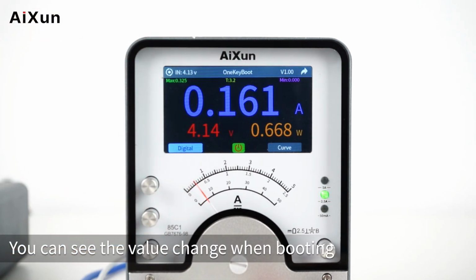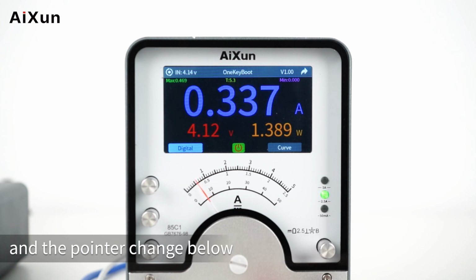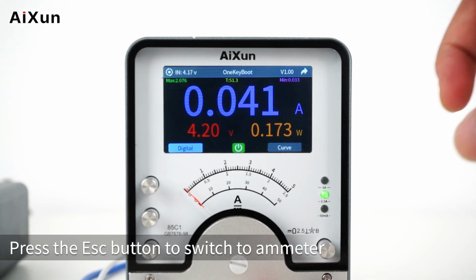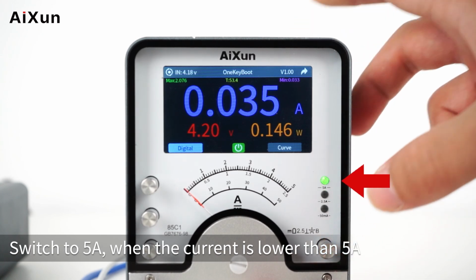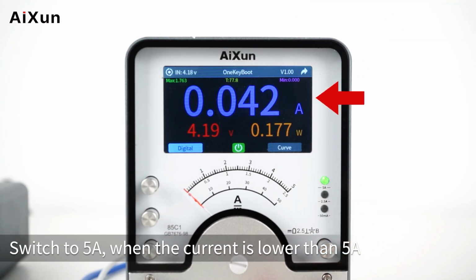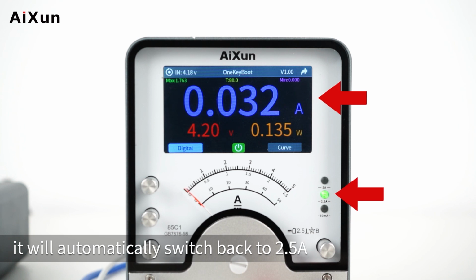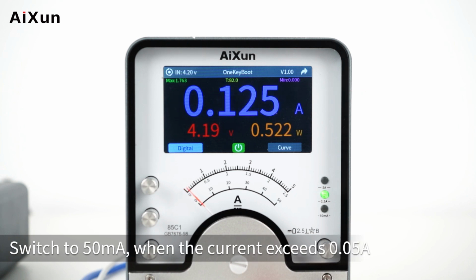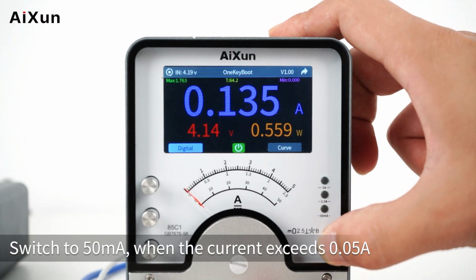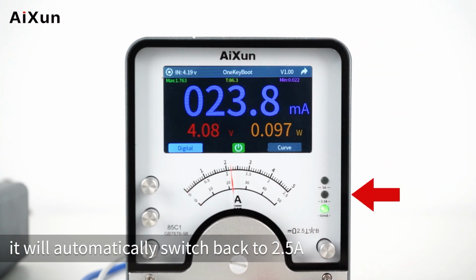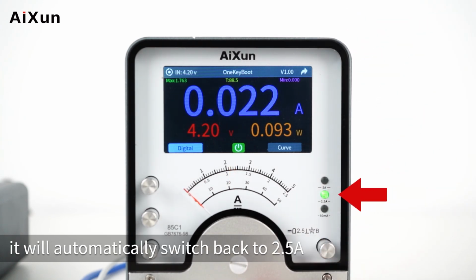You can see the value change when booting and the pointer change below. Press the escape button to switch to ammeter. Switch to 5A; when the current is lower than 5A, it automatically switches back to 2.5A. Switch to 50 milliamperes; when the current exceeds 0.05A, it automatically switches back to 2.5A.